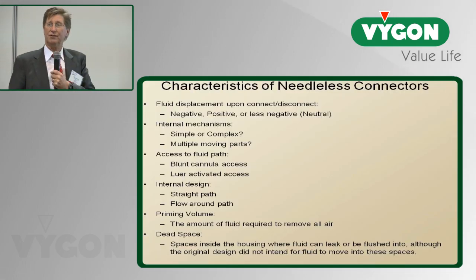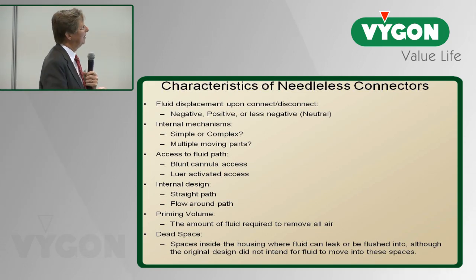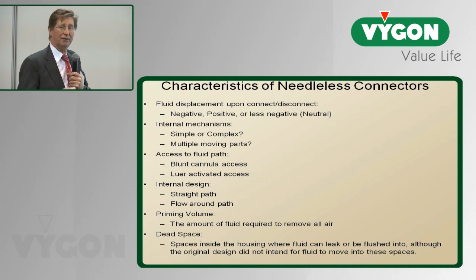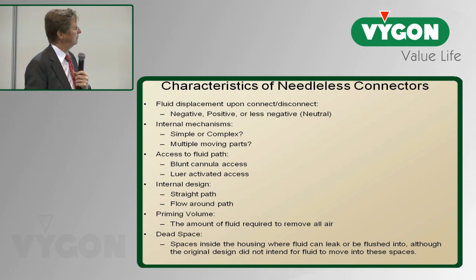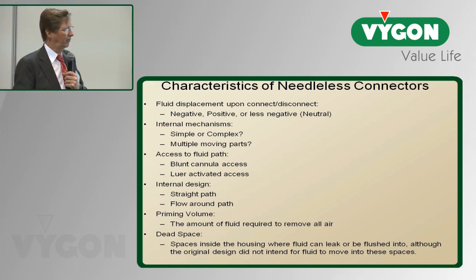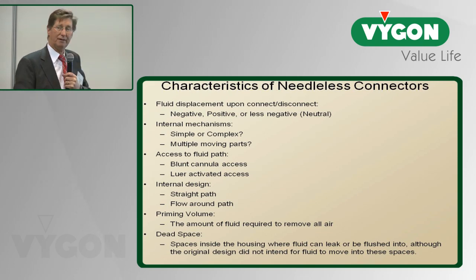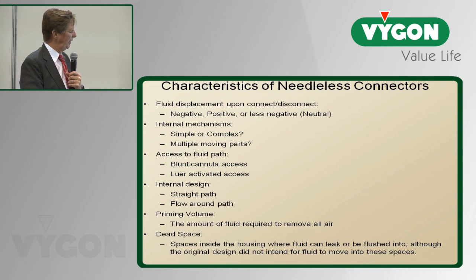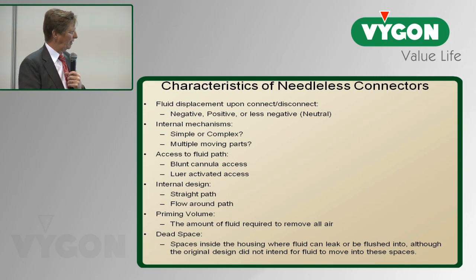If we look at characteristics of needleless connectors, these are the things you should be thinking about. First is fluid displacement upon either connect or disconnect—is it negative, positive, or neutral? Second, internal mechanisms—are they simple or complex, with multiple moving parts or no moving parts? Third, access to the fluid path—is it through a blunt cannula, luer-activated access, or split septum access? Fourth, the internal design—is the fluid path straight or indirect? And fifth, priming volume—what is the amount of fluid required to remove the air in that needleless connector?